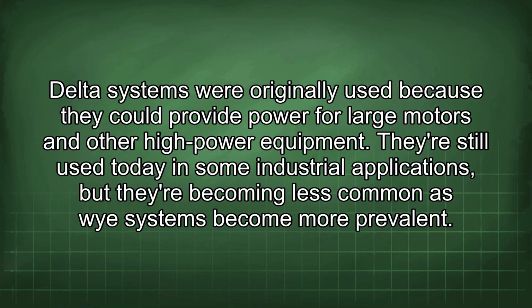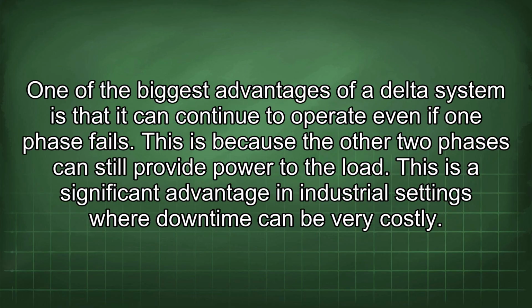Delta systems were originally used because they could provide power for large motors and other high-power equipment. They are still used today in some industrial applications, but they are becoming less common as Y systems become more prevalent. One of the biggest advantages of a delta system is that it can continue to operate even if one phase fails. This is because the other two phases can still provide power to the load. This is a significant advantage in industrial settings where downtime can be very costly.